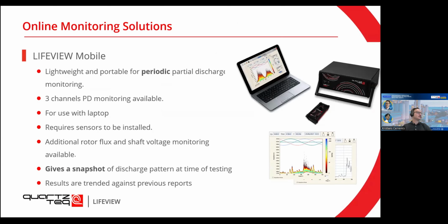And then finally, this is the LIFEVIEW mobile solution. So the one where I showed you this real case, the measurements were done with this mobile solution. Essentially, it's a portable, lightweight solution, comes together with the laptop, with the calibrator, with everything you need to perform these measurements. You can simultaneously, again, monitor the 3 channels. Again, this would need sensors to be installed in the machine, but like I said, you could have multiple machines with sensors installed, and then you come with the LIFEVIEW mobile and measure periodically the partial discharges here. Additionally, you can also measure the rotor flux and shaft voltage monitoring, which I'm going to explain a bit further on.